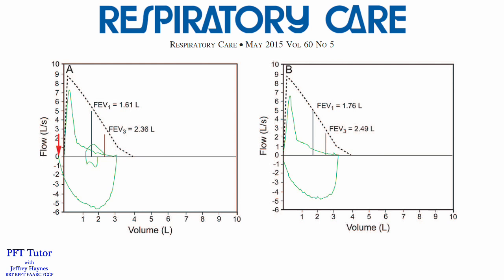In our letter, we included this example of the impact of submaximal inhalation on spirometry results. In panel A on the left, there is submaximal inhalation error. The end of the inspiratory loop exceeds the start of the expiratory flow as identified by the red arrow. In panel B on the right, the error has been corrected.